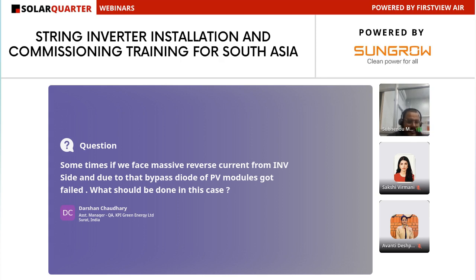Sometimes we face massive reverse current from the inverter side, and due to that the bypass diode of PV modules fails. What is to be done in this case? First, you have to check the string cables and floating on the DC side. It is only possible when there is a mismatch of strings in one MPPT, then it will only happen.